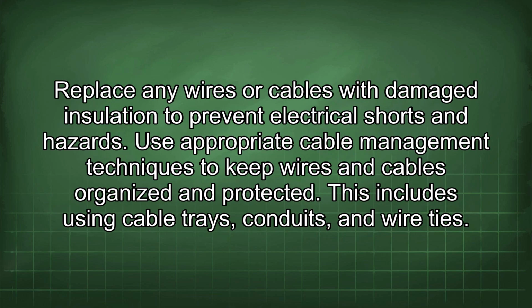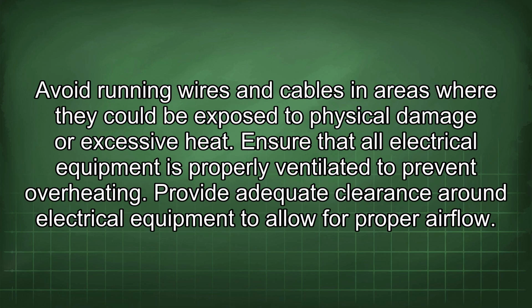Replace any wires or cables with damaged insulation to prevent electrical shorts and hazards. Use appropriate cable management techniques to keep wires and cables organized and protected. This includes using cable trays, conduits, and wire ties. Avoid running wires and cables in areas where they could be exposed to physical damage or excessive heat.